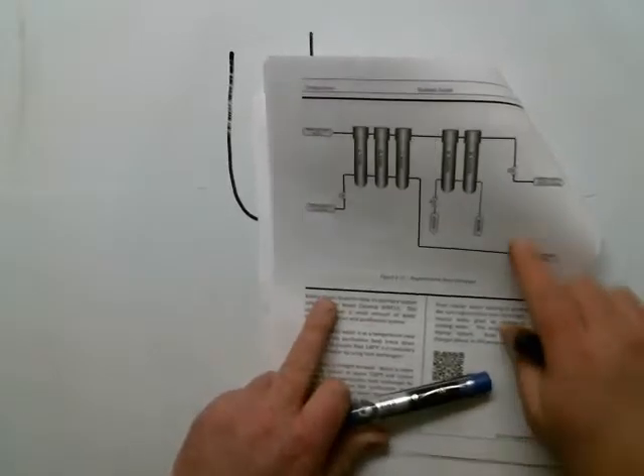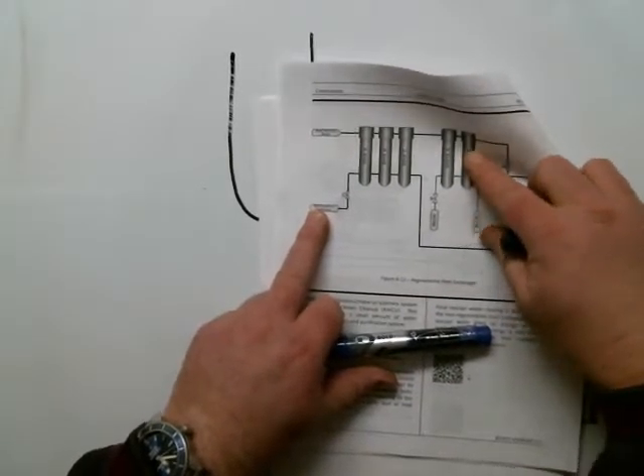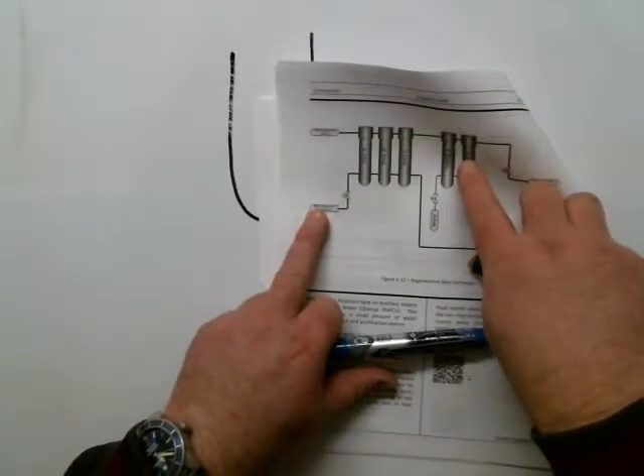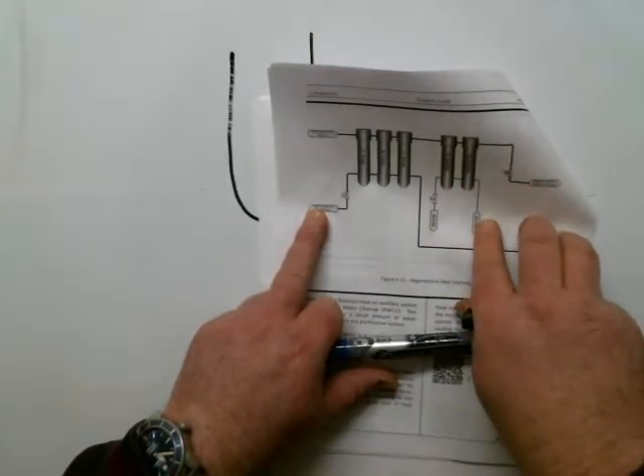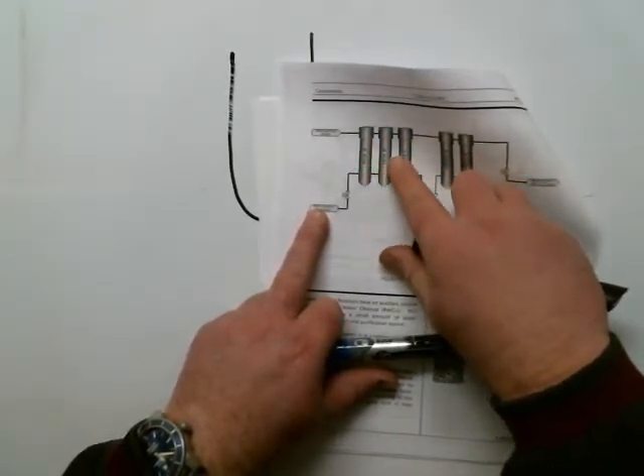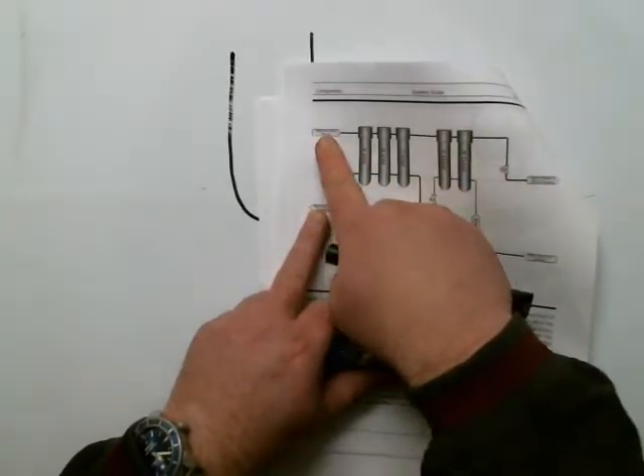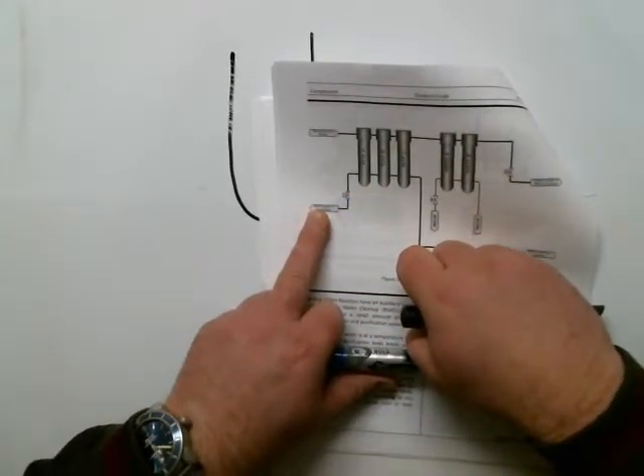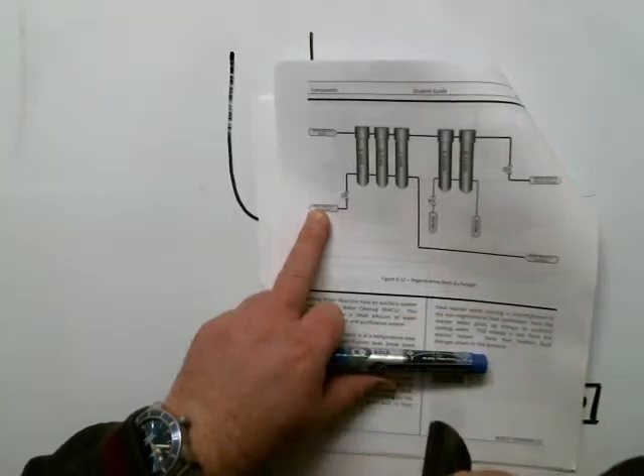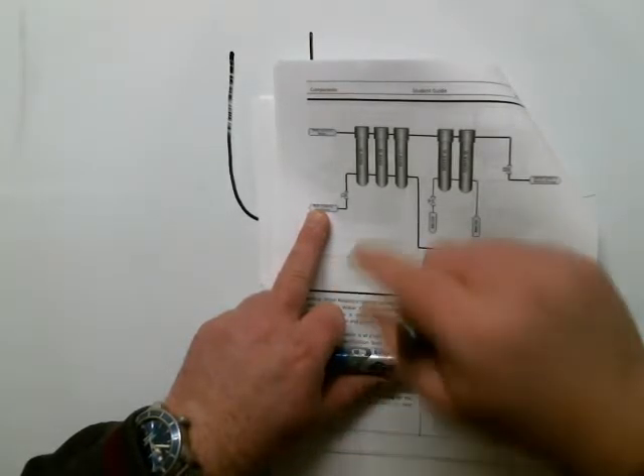And you can see that here. The non-regenerative heat exchangers are right here, and there's actually two of them in series in this drawing. And you can kind of see the cooling water. And there is no cooling water source here for the regenerative heat exchangers. The water just comes from the reactor vessel, or in this case it says from recirc.